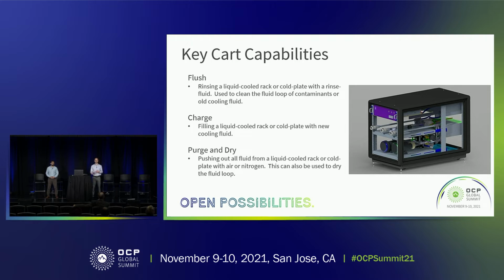Any cart within a data center, to functionally meet the requirements Saurabh pointed out, must be able to flush fluid, charge fluid, as well as purge and dry any fluid loops. Flushing uses a rinse fluid or even the cooling fluid itself to push out old cooling fluid and contaminants to clean the system. Charging is used when bringing a rack online, needing to charge it with new cooling fluid. Purge and dry is for maintenance or decommissioning a rack, using compressed air or nitrogen to push out old fluid and dry the system.